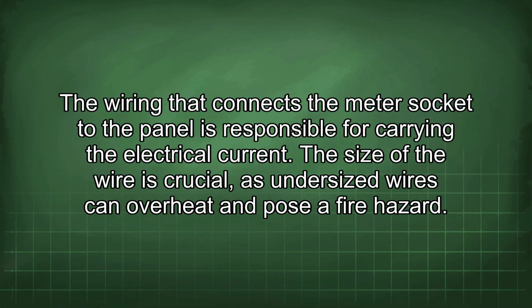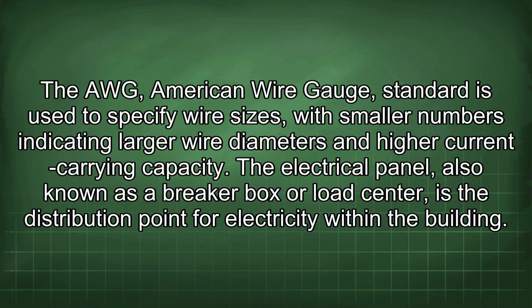The wiring that connects the meter socket to the panel is responsible for carrying the electrical current. The size of the wire is crucial, as undersized wires can overheat and pose a fire hazard. The AWG, American Wire Gauge, standard is used to specify wire sizes, with smaller numbers indicating larger wire diameters and higher current carrying capacity.